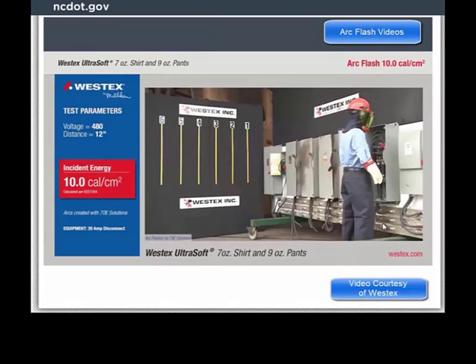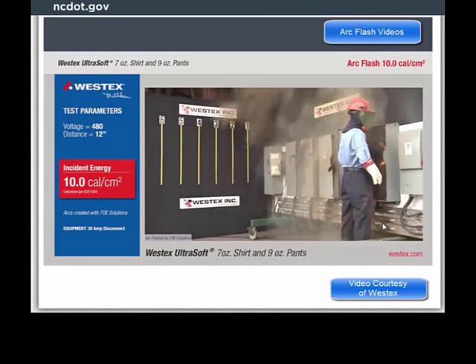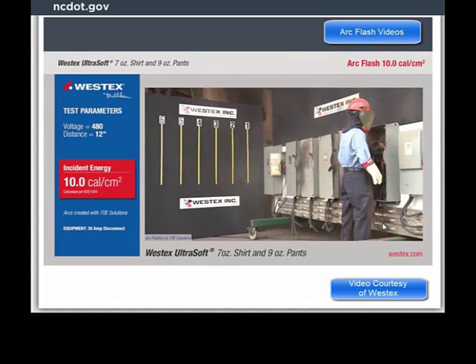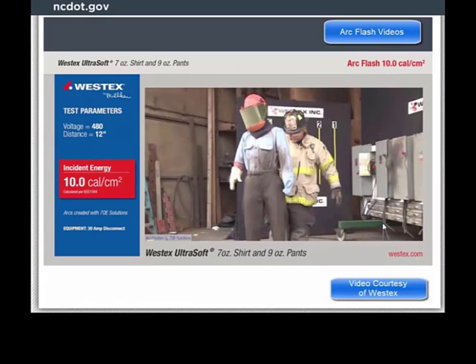This mannequin is wearing Westex Ultra Soft shirt, pants, and balaclava. We have a 10-calorie arc and a 480-volt disconnect. And after the arc's over, there's no fire on the garment. You do see some fire in the disconnect. There's something continuing to burn in the disconnect. But the Ultra Soft has done its job. You can see in the still frame here, there's no significant damage of the garment and no break opens.